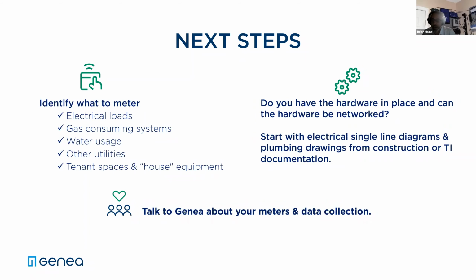So the first place to start is to break out some of those drawings, electrical single line diagrams, plumbing as-built diagrams, all that sort of stuff from construction, and any TI documentation you have. Get all of that together and you can identify exactly what needs to be metered. Does that tenant have a supplemental AC unit? Well, you're going to need to meter not only the electrical but the chilled or condenser water consumption for that. So a lot of information we need to gather here.